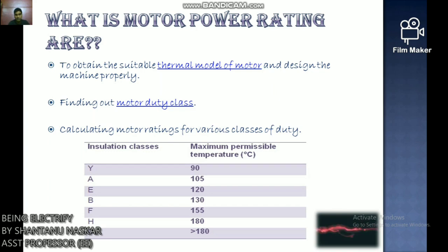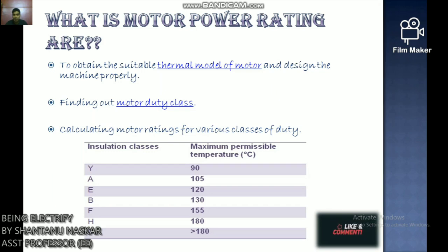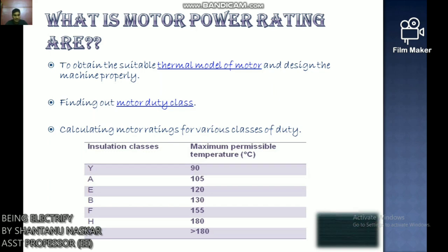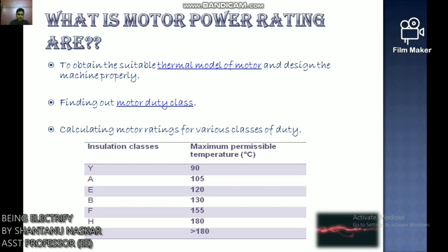When the motor has insufficient rating there will be frequent damage and shutdown due to overloading. On the other hand, if the power rating is decided too liberally, the extra initial cost and loss of energy due to operation below rated power makes this choice uneconomical. Another essential criterion is that during operation, motor heat is produced inevitably due to I²R (ohmic loss) and friction within the motor.